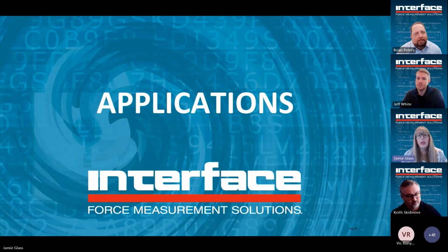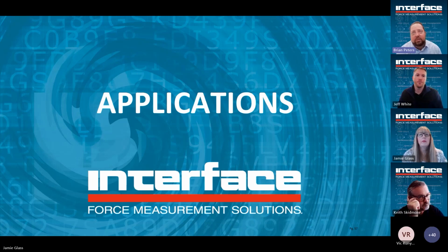And just one other question, and I know you covered this early on, but you talked about safe overload, what that means, and will the load cell still meet specs if loaded to 150%? Yes. Well, it should still maintain meeting specifications within the safe overload. Most sensors will be 150%. Some are more, some might be less. But yes, that's not with frequent use. Frequent use cannot be guaranteed that would be true.